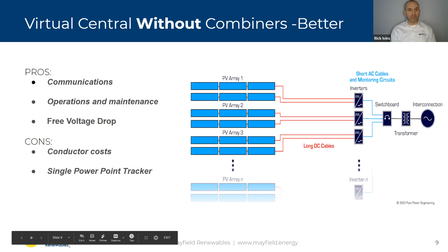It's much easier to install, and the O&M is easier too. If you need to do any testing, commissioning, recommissioning, or troubleshooting, the majority of the work is done right at the pad where all the inverters are, and you don't need to walk from inverter to inverter. Even simple things like opening them up - otherwise you'd have to go open them all, do your tests, then go back and close them all up. Lots of walking and trips around. This makes it a lot easier from the O&M standpoint.